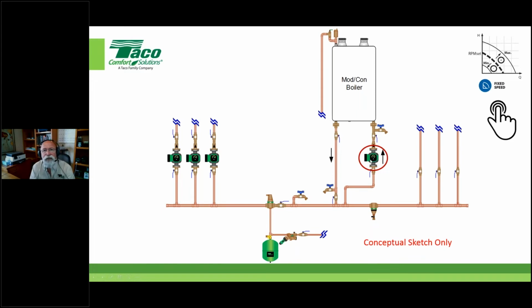There's nothing that's going to give it a hydraulic change so that it would have the input to make a decision to speed up or slow down. So do not use an automatic mode for that pump. Okay, it just won't ever get the information to change its speed. It may or may not be enough. Now I'll show you one application where we're going to say, go ahead and do this, but it's only once you've dotted your I's and crossed your T's, and we'll show you that, okay? By all means, it's being done, it's done successfully, but it doesn't make a lot of sense if your expectation is that the pump's going to speed up and slow down, because it will not.